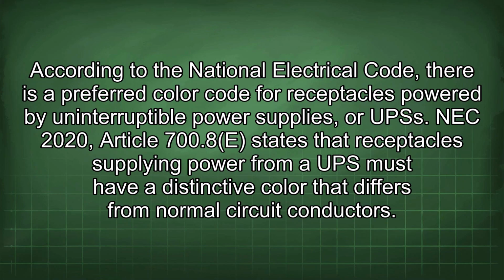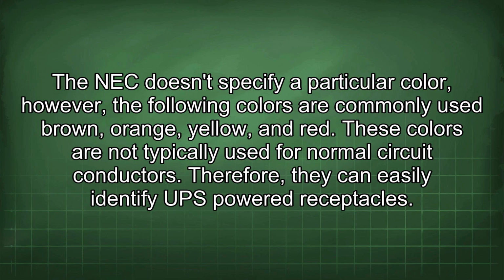According to the National Electrical Code, there is a preferred color code for receptacles powered by uninterruptible power supplies, or UPSs. NEC 2020 Article 700.8e states that receptacles supplying power from a UPS must have a distinctive color that differs from normal circuit conductors. The NEC doesn't specify a particular color, however, the following colors are commonly used: brown, orange, yellow, and red. These colors are not typically used for normal circuit conductors. Therefore, they can easily identify UPS-powered receptacles.